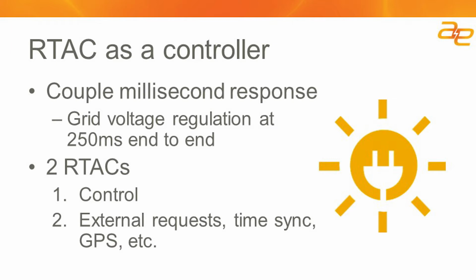And because it's also used often as an RTU or a data concentrator device, it has the ability to do GPS time synchronization and interface with external utilities. So it is the device that I would prefer to use if a customer wanted to interface with a transmission operator to do AGC, or automatic generation control, where the utility themselves would just send in real time a SCADA command for what the plant should do for an output. We wouldn't need manual controls or operators to go in and change a set point in order to have the system respond. It can be tied directly to the balancing authority to take the commands and adjust the plant output.